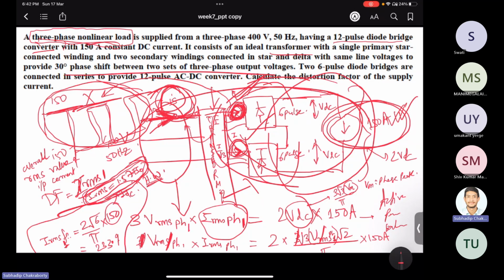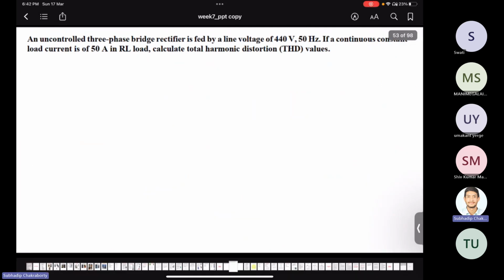So power balance will only work for fundamental determination. Overall signal you need to do by seeing the waveforms only. So 1.57 times I naught will come as IRMS overall. So divide these two, and then the distortion factor will come out to be 0.989. Just see how it is coming, and answer I gave you, okay? Because we need to move on to the filters. But keep your fundamentals correct, and you do this homework and tell me in the group how you are arriving at that value. So not everything has formula, right? You have to do something by hand also and then see. You can assume that as a formula, but it will not work for all cases.